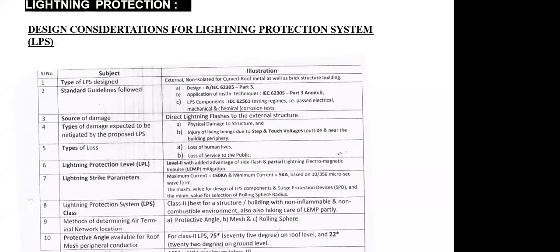For the lightning protection level, we have selected level 2, which gives the added advantage of protection against side flash, partial lightning and electromagnetic impulse, because it creates a flux, what we call EMF. To avoid this, the protections should follow level 2. Lightning striking parameters: maximum current is 150 kiloampere, minimum current is 5 kiloampere, based on a 10/350 microsecond waveform. You can imagine it is a huge current flow, because in the panel discussion with IEC 61439 and other panel design considerations, we considered a maximum of 65 kA, and in case of lightning it is as high as 150 kA, the maximum it can generate. So you can imagine how massive it is.